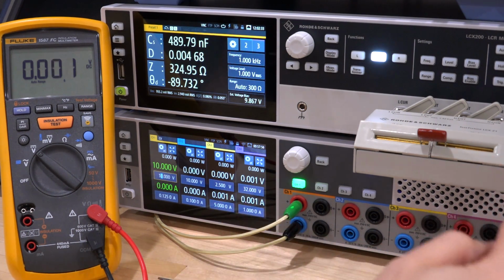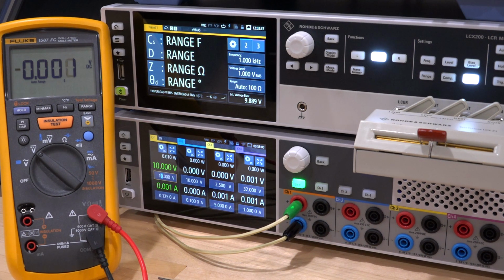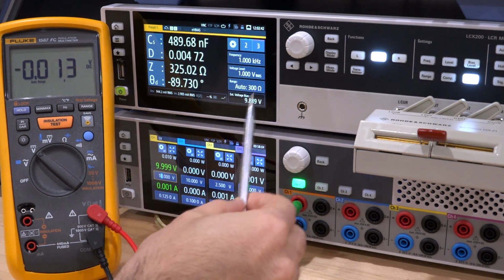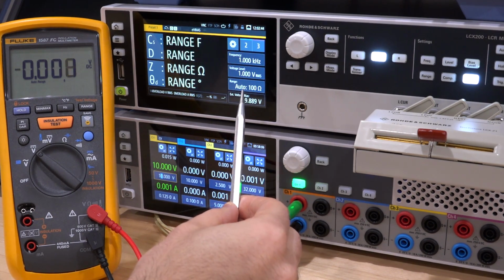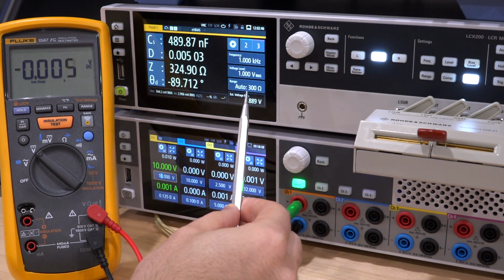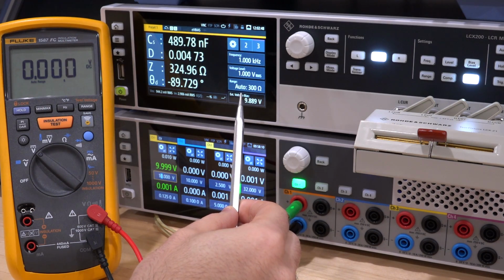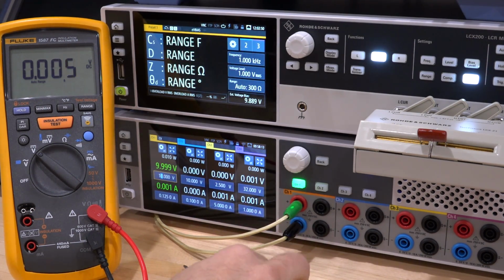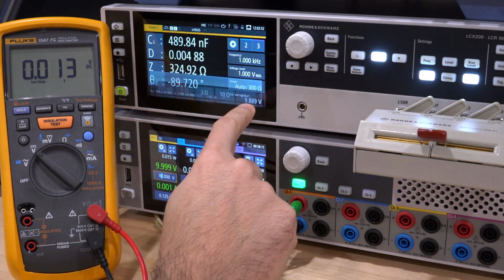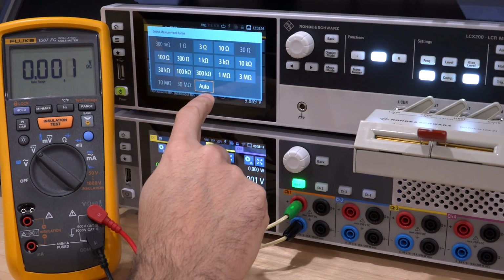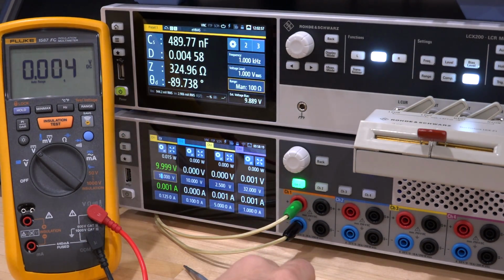So now we can go ahead and enable the bias, and the 10 volts should appear across the capacitor. Let's go enable it. There we go, so it's going to charge the capacitor briefly, and then it gets into this condition where it's hunting for which range to use. And that's why I wanted to have a bit more control over the auto-ranging parameters and the algorithm so that the user doesn't get into a situation where it keeps hunting. We can nail down the auto ranging and force it to stay within one range. We can set, for example, 100 ohms here, and then it settles down.